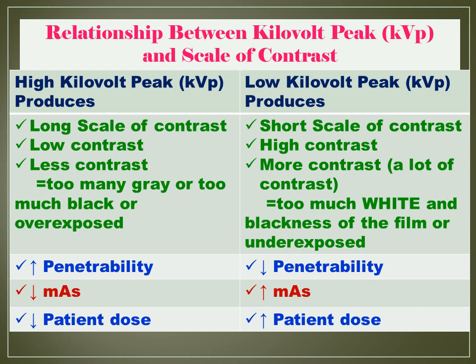Since high KVP results in an overexposed film and low KVP results in an underexposed film, we need to solve the problem. We apply the 15% rule — to change the KVP by 15% while changing the MAS by one half or double. This will be discussed next time.